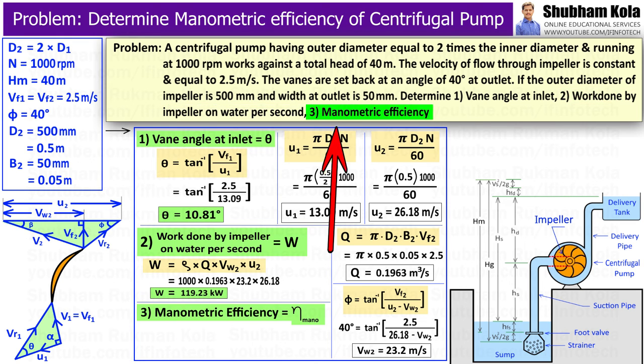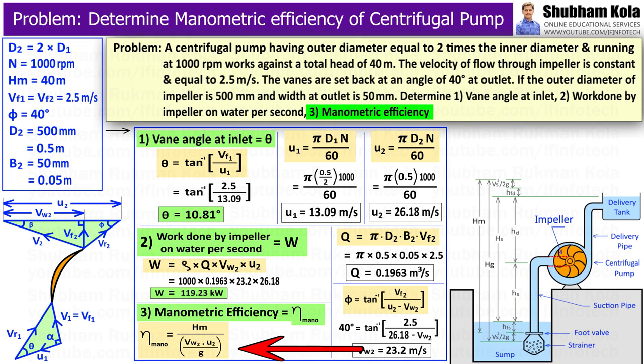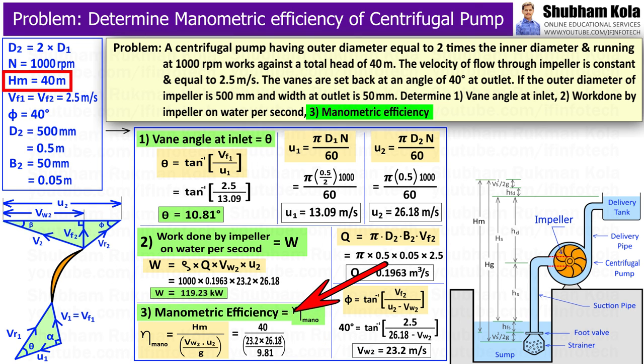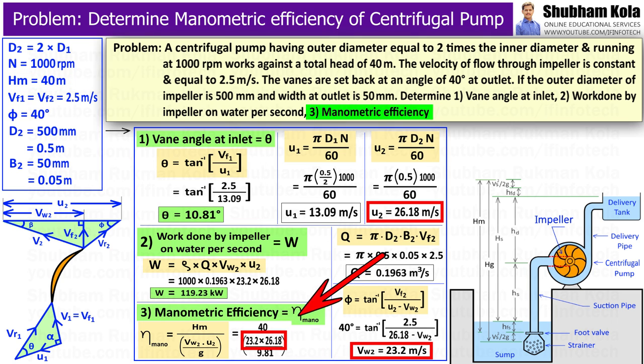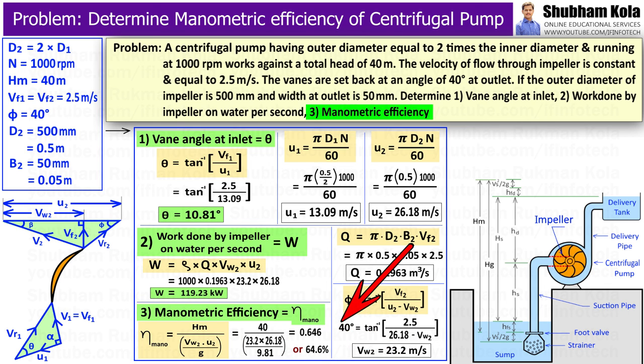Finally, manometric efficiency is given by the formula: manometric head HM divided by the head imparted by the impeller, which is Vw2 × U2 / g. Here HM = 40 m, Vw2 and U2 are already calculated, and g = 9.81 m/s². Calculating this gives manometric efficiency = 64.6%.